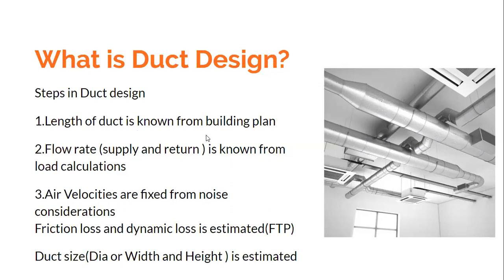Similarly, you determine the length of the duct from the room to be cooled back to the air handling unit — that is called the return duct. So the length of the duct is known from the building plan. The other important thing is how much quantity of air needs to be supplied for achieving the inside design conditions. That supply quantity is calculated during the load calculations.